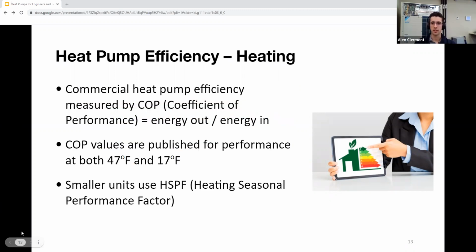So in heating, the main efficiency metric that's actually looked at is COP. So how many BTUs of heating can be outputted from a system versus how much electricity it takes to do so. Now these are currently measured by AHRI as well, which is a testing association for all these types of equipment. Unfortunately, AHRI only publishes COP at 17 degrees and 47 degrees, which is not really a true representation of our northern climates here up in New England. And there's actually talks about publishing COP data at lower temperatures.